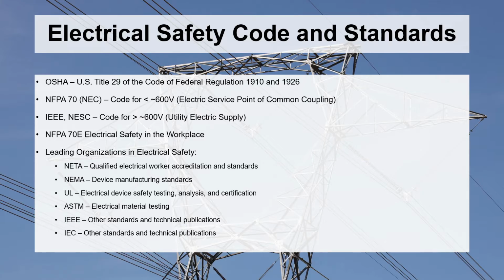A word of note: the NFPA 70E, 70, NESC—these are not design guides. They won't teach you how to build or wire a house. Rather, it's a set of codes that, given your conditions and electrical inputs—say you're installing a motor in a hazardous gas environment, or working with emergency fire equipment—will tell you the minimum equipment needed to install it safely, or in the case of 70E, what safety equipment and training you need to do it safely.